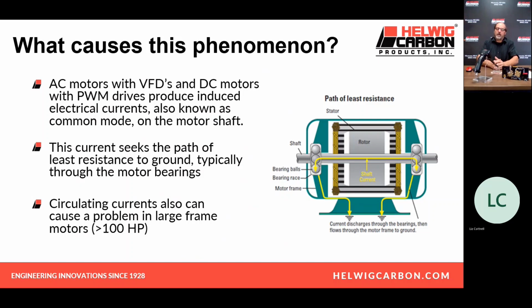What causes this electrical wear? Motors driven from VFDs or other PWM sources generate an imbalance in the motor shaft, and that ultimately causes a buildup of static on the motor shaft. That static builds and builds until it finally finds a path to ground, typically through the drive end bearing, arcs through the bearing to ground. The shaft builds voltage, arcs through the bearing to ground. Each time this happens, and it happens quite frequently, it damages the raceway, the ball bearing itself, and the grease. The more this occurs, the worse the problem becomes, and it begins to snowball on itself.